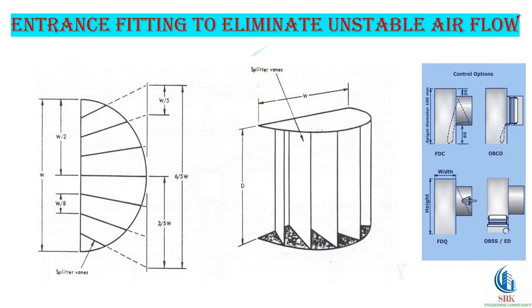Construction dimensions for the special entrance fitting. Tests have shown that without this fitting, air will first rotate clockwise within the plenum. Then, with an off-on cycle of the equipment, air rotation may reverse and rotate counterclockwise. This changing direction affects the amount of air delivered to each branch and can upset the balance in the system. Use of the special fitting also reduces the box plenum pressure loss by as much as 80%.